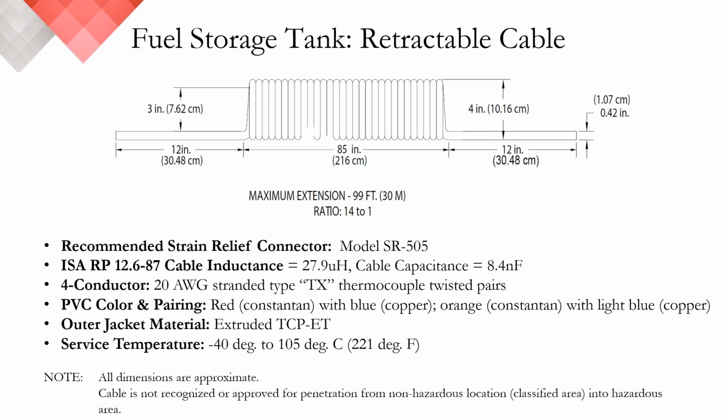This is the data sheet for the retractable cable. The maximum extension is 99 feet, which is 30 meters. I'd like to point out that this retractable cable can be wired for both the standard Protectowire PHSC or the CTI series CTI-X detector, depending on the application that you have, what system you're using. Again, the same retractable cable can be used for both the PHSC Protectowire and the CTI Protectowire.